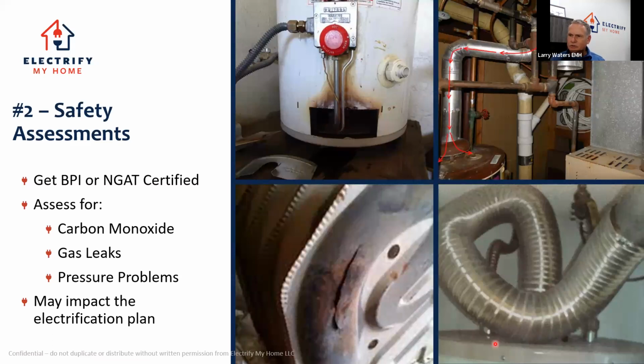This one down here, this is the top of a water heater. And this is really just an example of why Home Depot should not sell water heaters to civilians. Because exhaust gases have to travel out via gravity. They're not under any kind of pressure. So trying to have one go through a roller coaster where it's going downhill, this is never going to vent. All the exhaust in this house was coming into the house just because a homeowner came up with an idea that he wanted to do this himself.